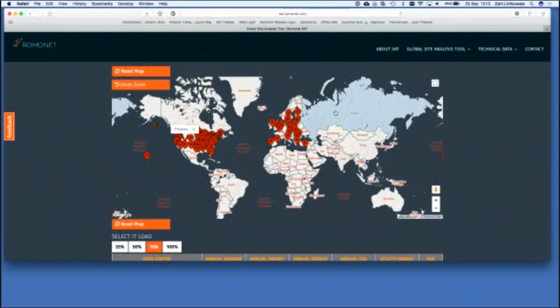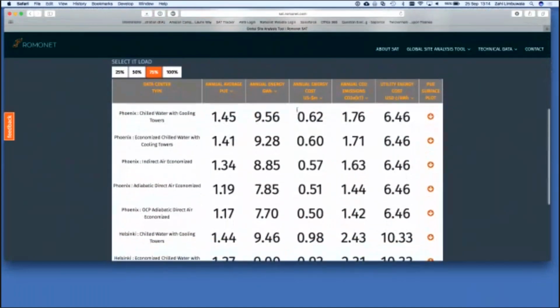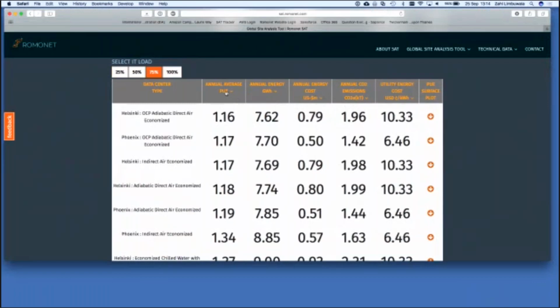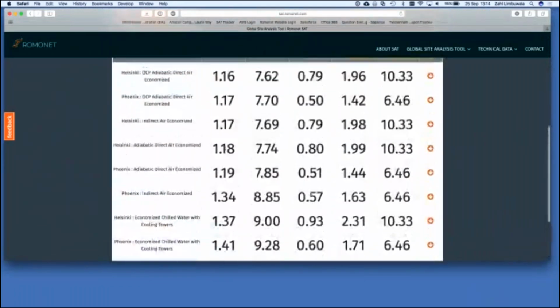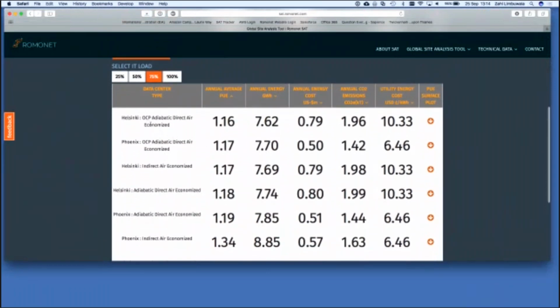First set of results, and I was going to pick Helsinki as the second. A bit difficult to see from this angle. Right, so I'll do a sort on annual average PUE. What you'll see here is I've sorted low to high PUE for those two locations, and we should see the OCP adiabatic come out top. That's generally because the OCP model in here is essentially a variant of the adiabatic model, which is just underneath here. Interestingly, the indirect one performs quite well in Helsinki as well.